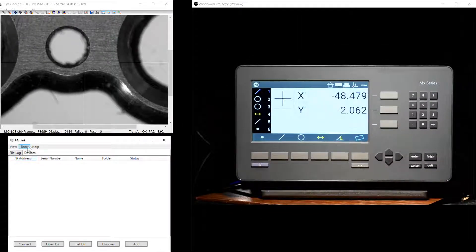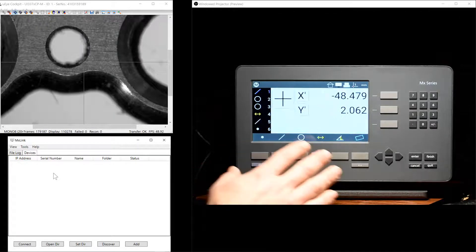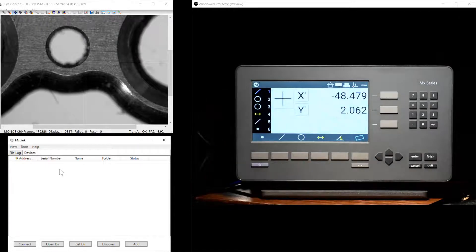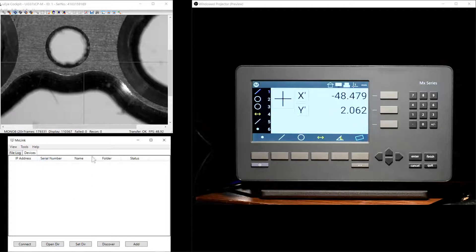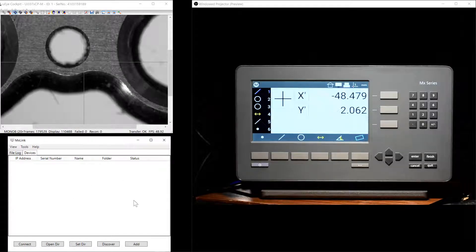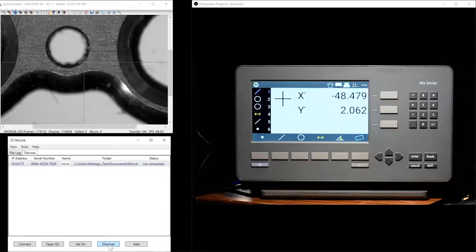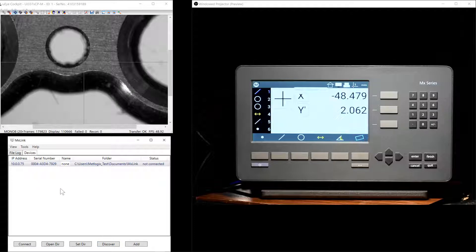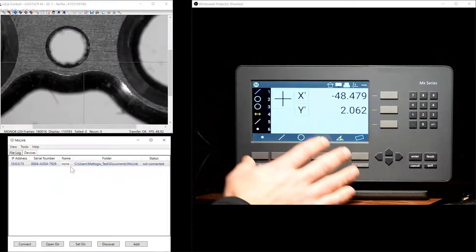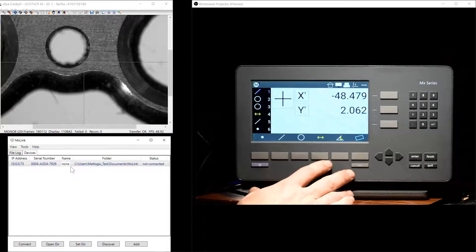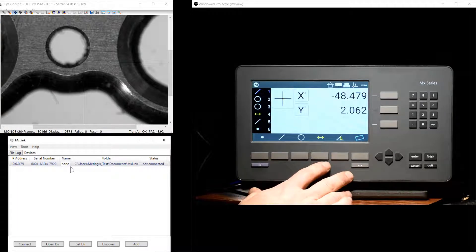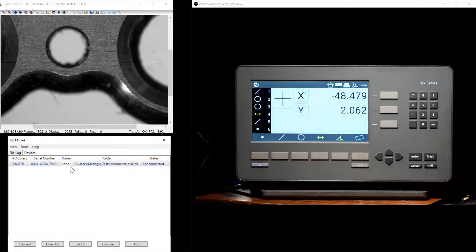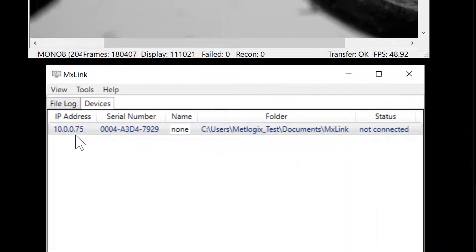It's in this main Devices tab that we'll begin the process of pairing our MX200 readout with the connected PC application. The first step will be to press the Discover button, as seen here. The MXLink application will go out and try to detect all licensed MX200s that are detected on the same network. Any detected devices will be listed here in the Devices tab.